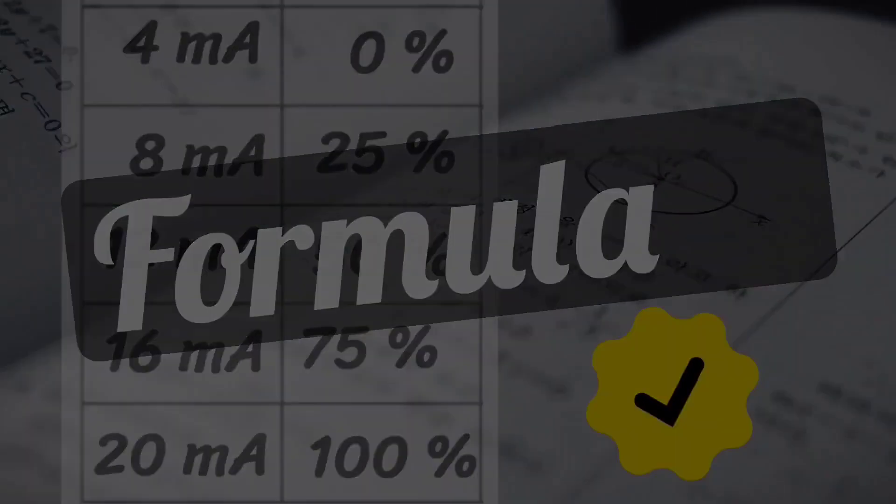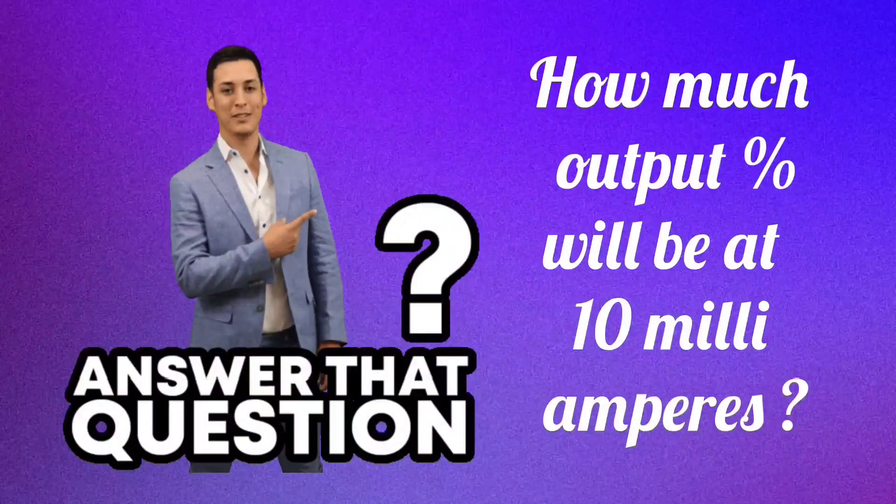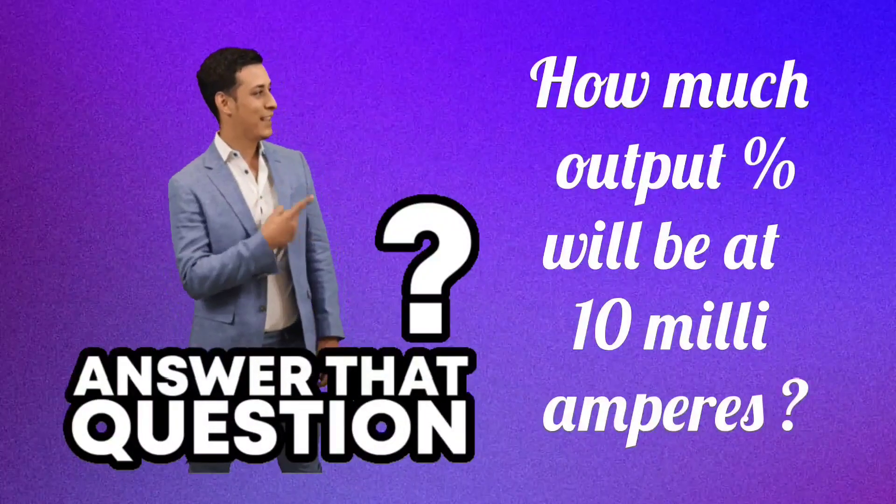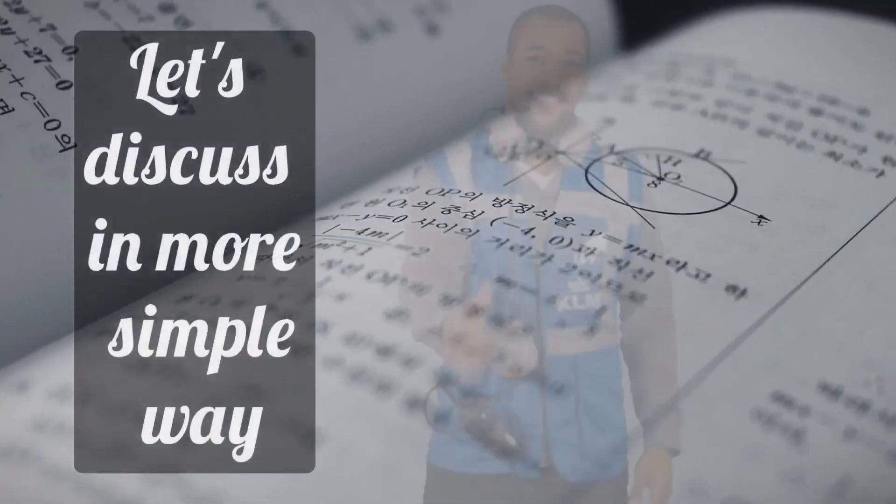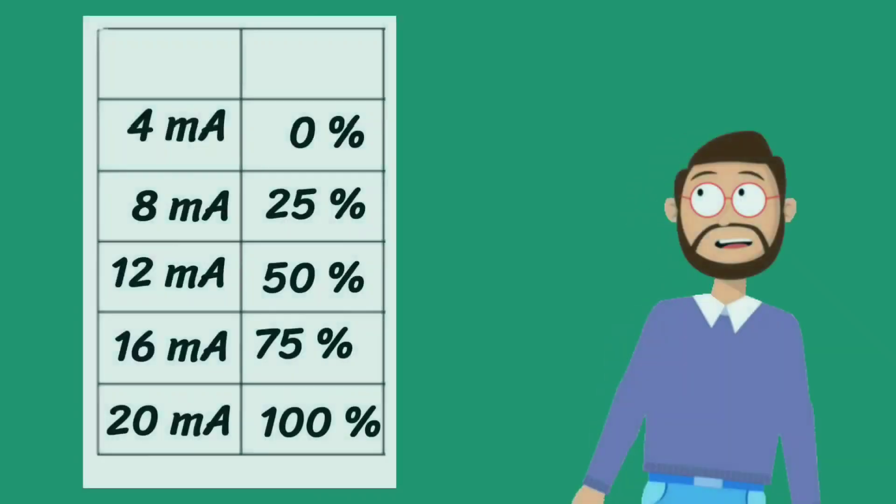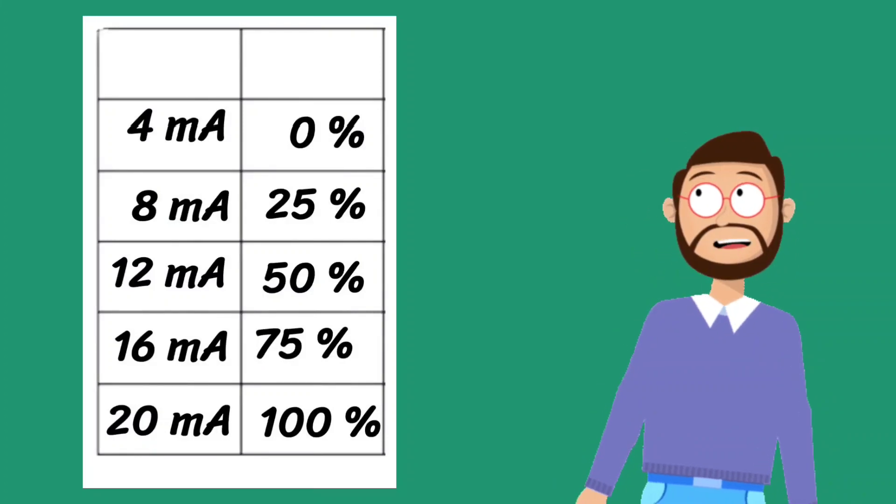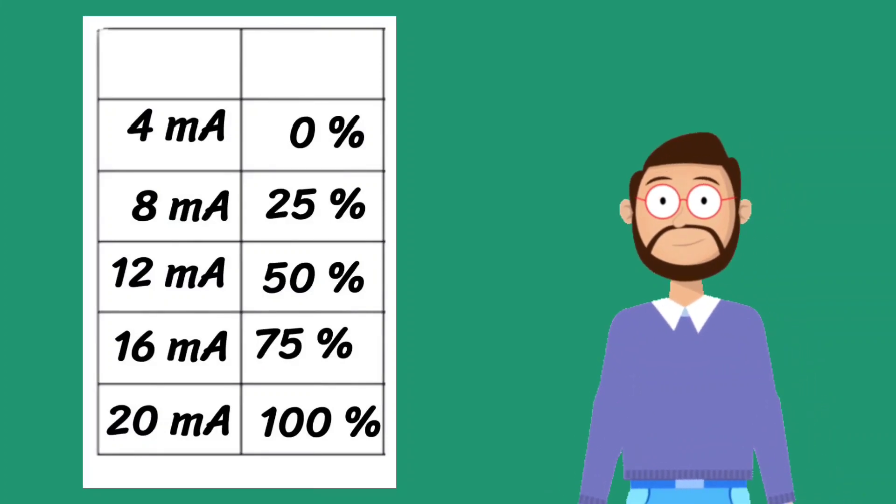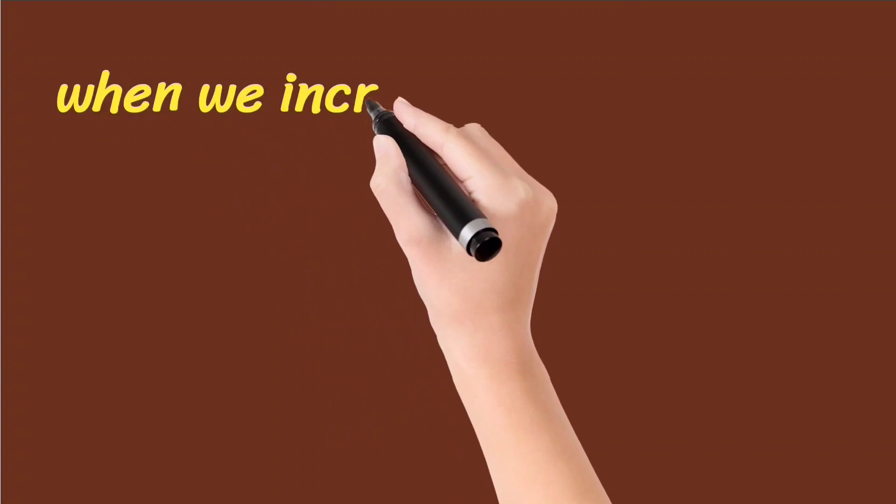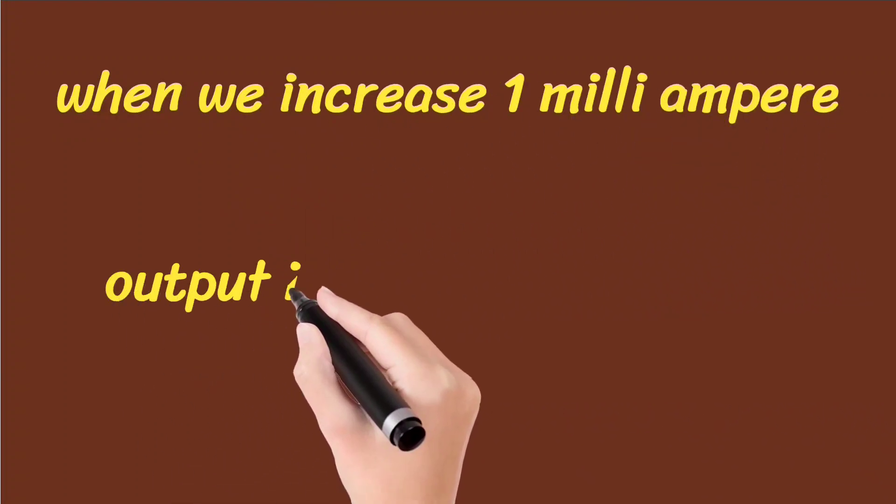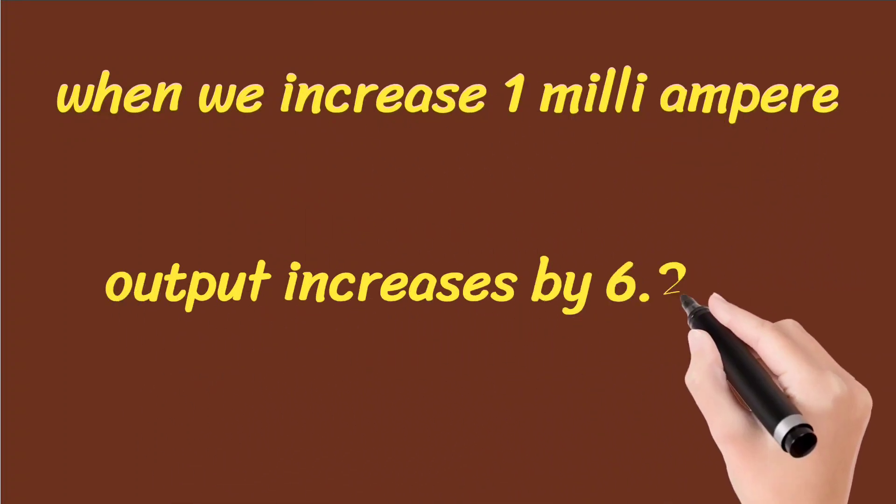Now your formula has also been verified. Now you people reply, what will be the percentage output at 10 milliamperes. Let's discuss in more simple way. Let's look at the table once again. When you look at the table, you will find that on 1 milliampere signal, 6.25% output is increasing.